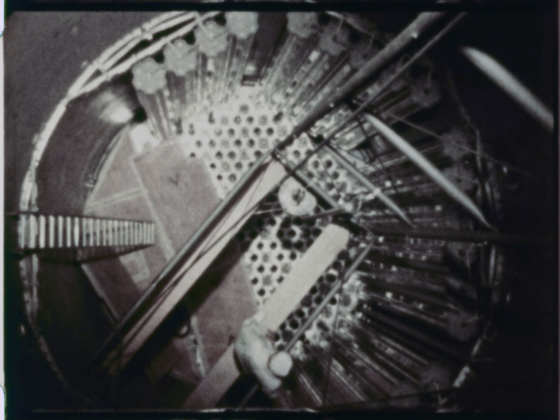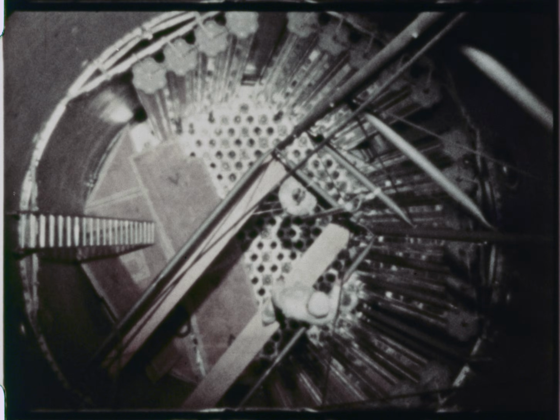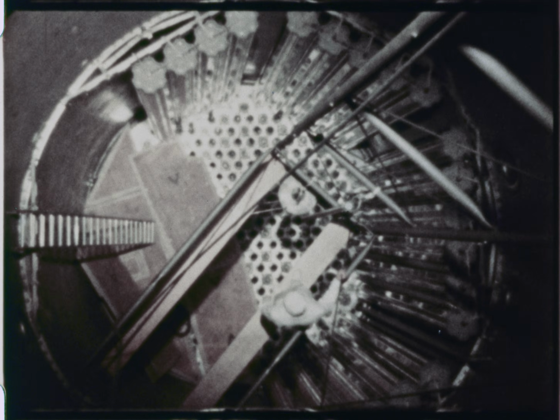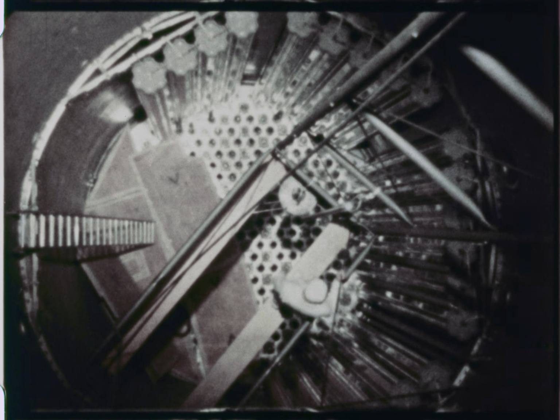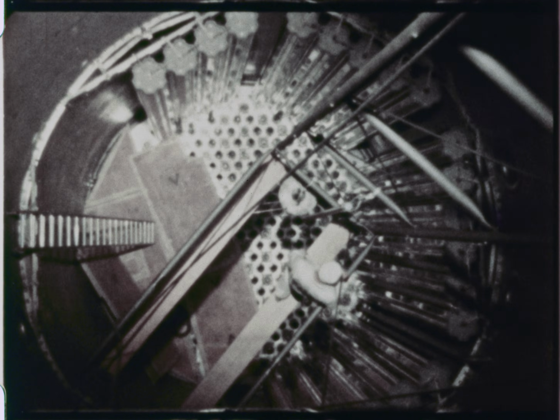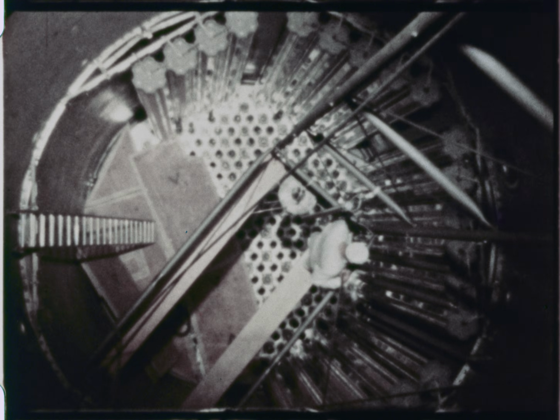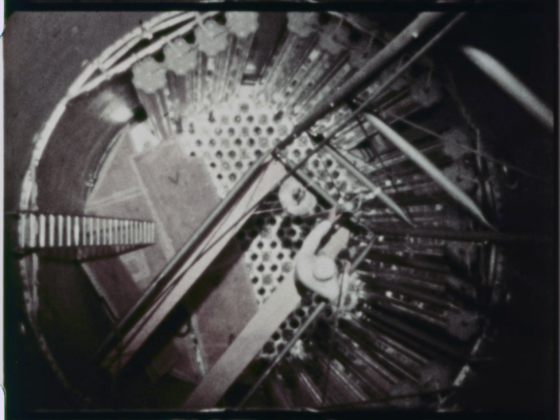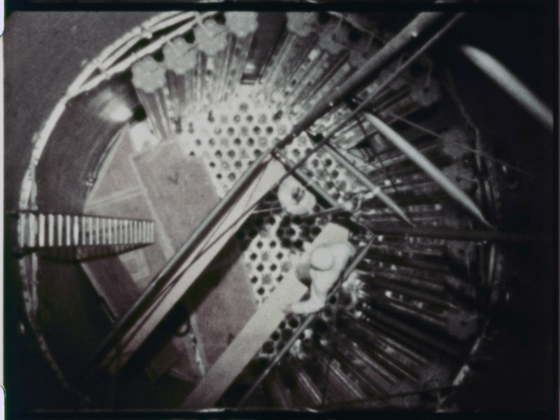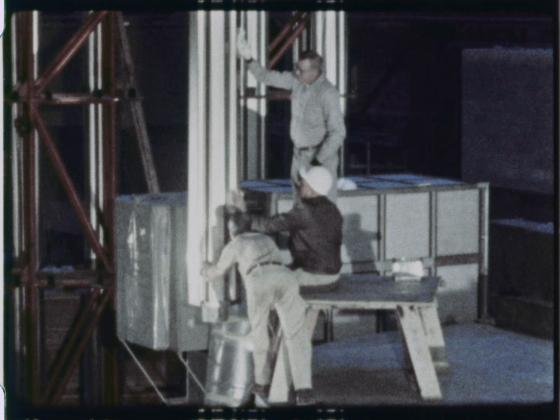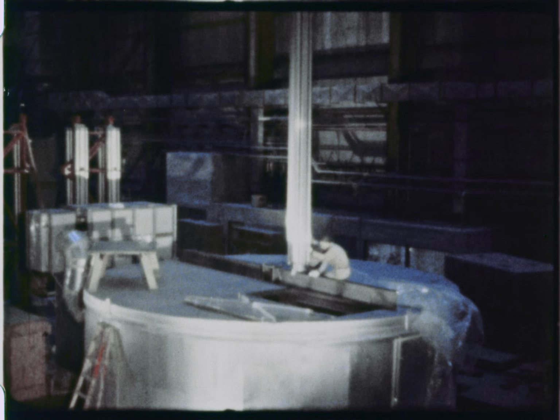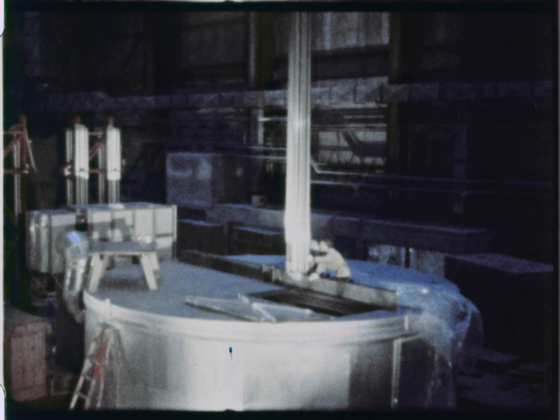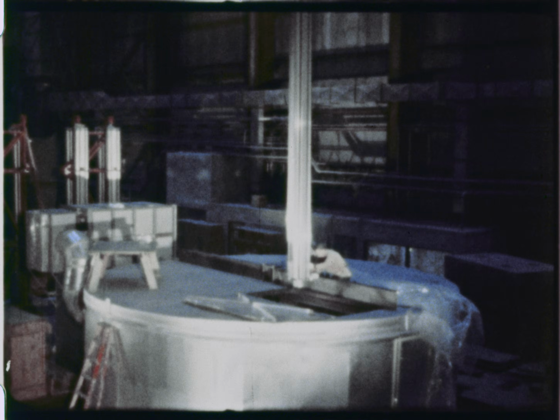Spacers maintain a 16/100 inch clearance between moderator elements. In addition, core clamps are provided on the internal vessel wall to hold the moderator elements in place. The clearance between the elements permits the circulation of small amounts of sodium to cool the graphite. To avoid contamination, components were continually cleaned during installation to remove lint or other foreign matter.